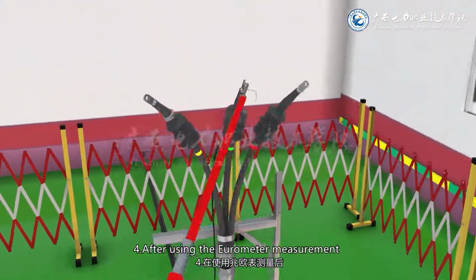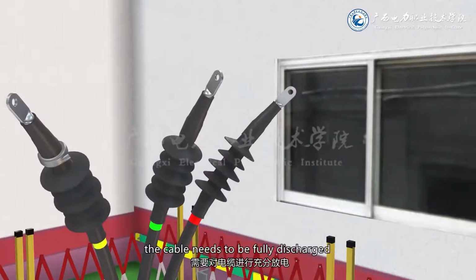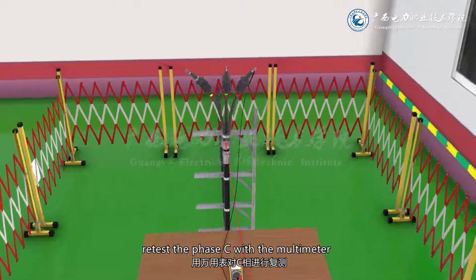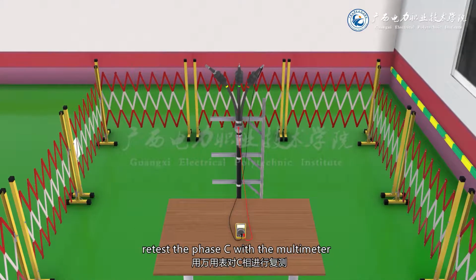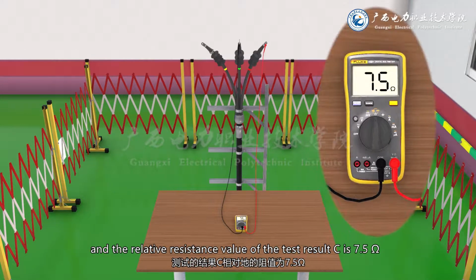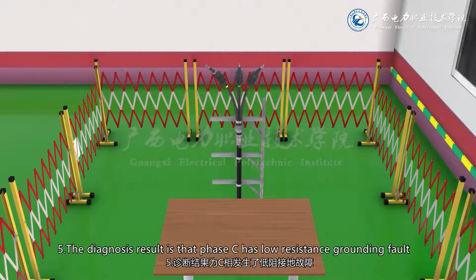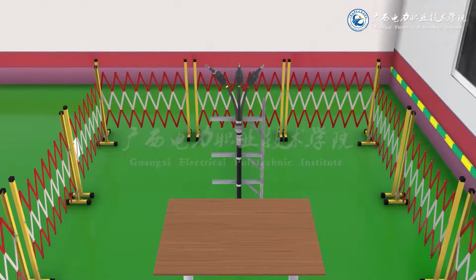4. After using the megohmmeter for measurement, the cable needs to be fully discharged. Retest phase C with the multimeter: the resistance value of phase C is 7.5 ohms. 5. The diagnosis result is that phase C has a low-resistance grounding fault.